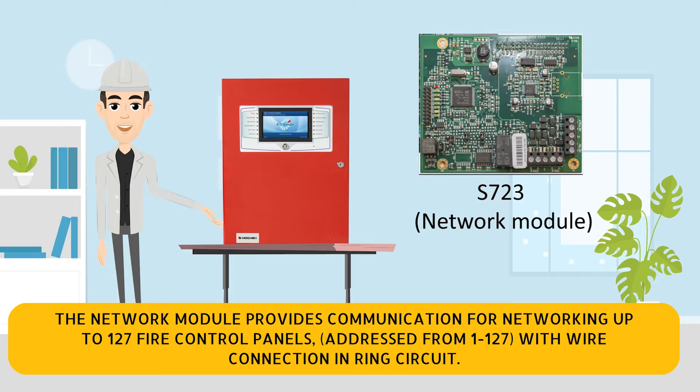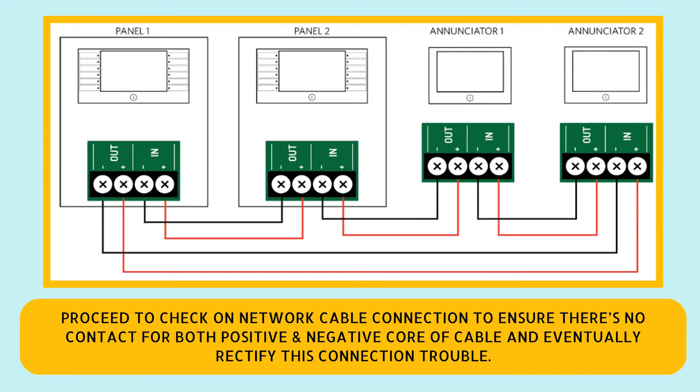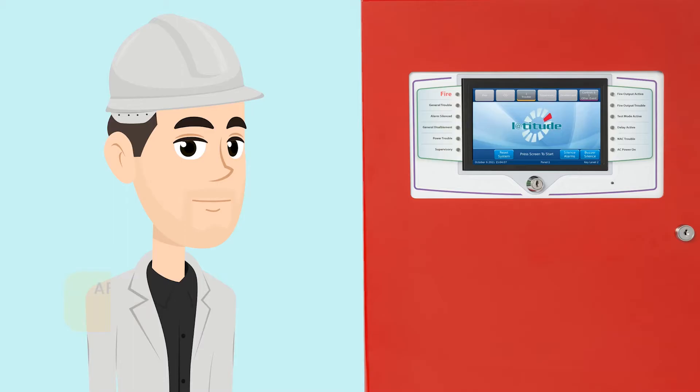The panels are addressed from 1 to 127 with wire connection in a ring circuit. The network module is constantly monitoring the incoming and outgoing circuit. A network short circuit trouble indicates there is a connection trouble — the positive and negative core of the network cable came in contact. Proceed to check the network cable connection to ensure there is no contact between both the positive and negative core of the cable.